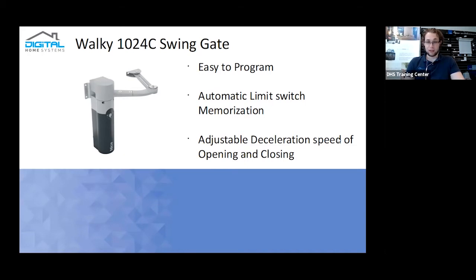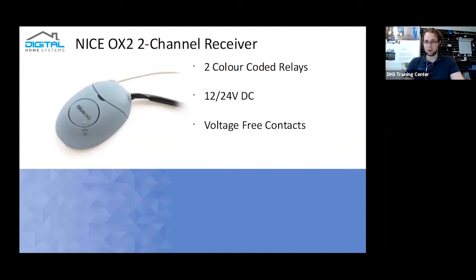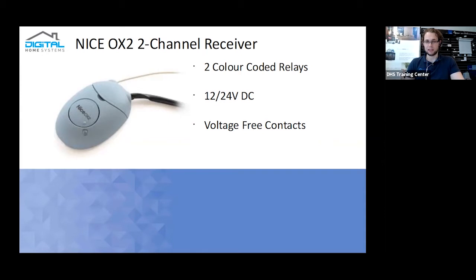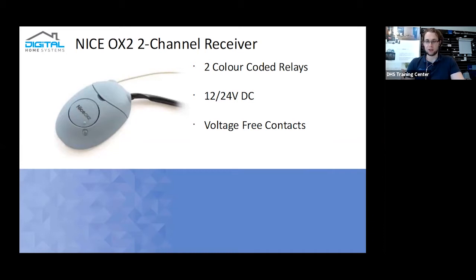The third one for it is actually a new device that we actually recently got, which is the Ox two-channel receiver. It's just a very simple two relay outs, two color-coded so not easy to mix up. Can support both 24 volt and 12 volt. The switch between that requires you to insert essentially a stopper into it which actually comes with the device itself. So if you need to set it up for 24 volts you can set it up normally. If you need to set it up for 12 volt, you very easily put the stopper in and essentially drops it down. It also has voltage-free contacts as well, so you can use it to trigger pretty much a large variety of devices from 5 volt to 24 volt without much issues.